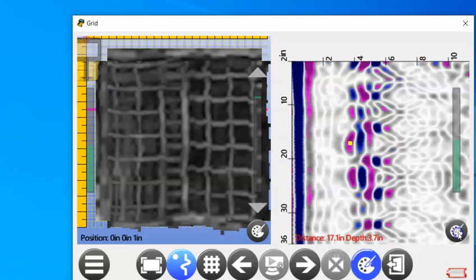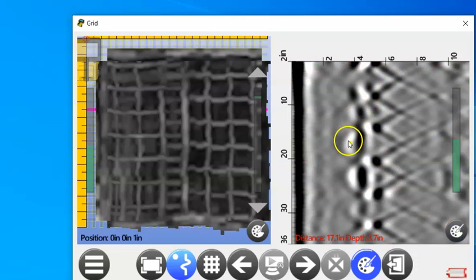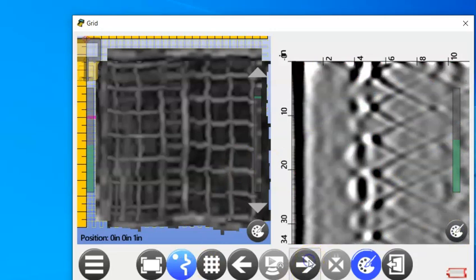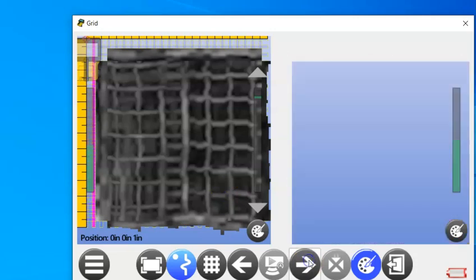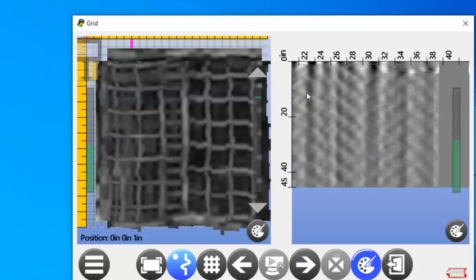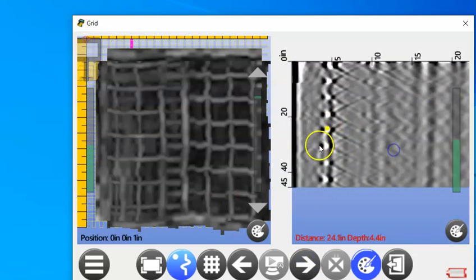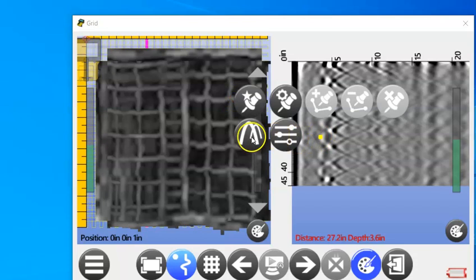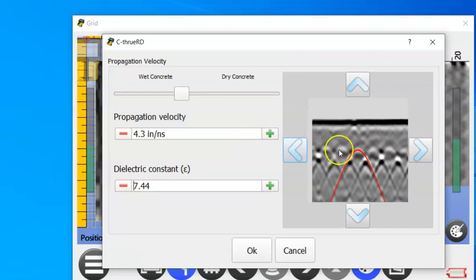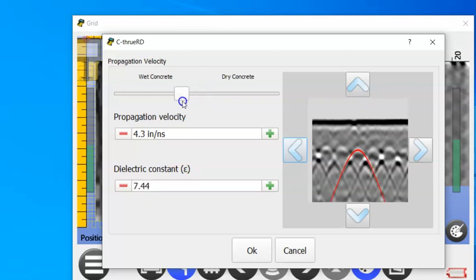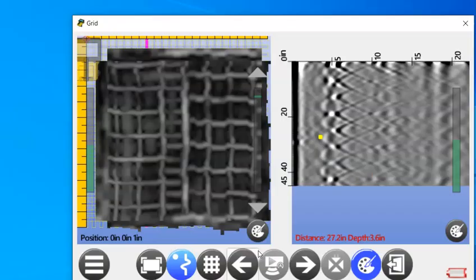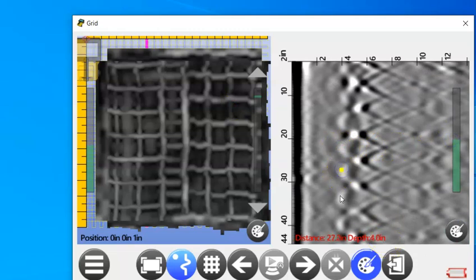One of the other things that we can change is going to be the migrated data. We're doing a Hilbert transform now. Let's do first off, like you would with any survey, a hyperbola fit. You can either right-click on your remote desktop or push and hold with your finger on the C-thrue, go to the hyperbola fit. It actually looks pretty good here. That's going to update our survey to get a little more accurate depth here, and you always want to do a hyperbola fit. And now we're showing this rebar at about 3.8 inches.